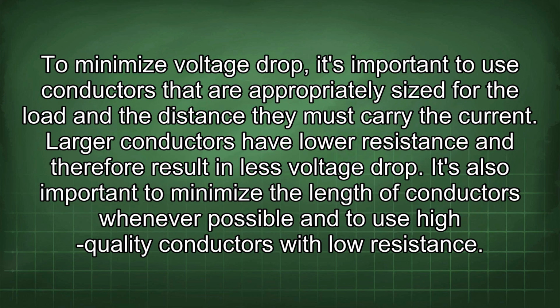To minimize voltage drop, it's important to use conductors that are appropriately sized for the load and the distance they must carry the current. Larger conductors have lower resistance and therefore result in less voltage drop. It's also important to minimize the length of conductors wherever possible and to use high-quality conductors with low resistance.